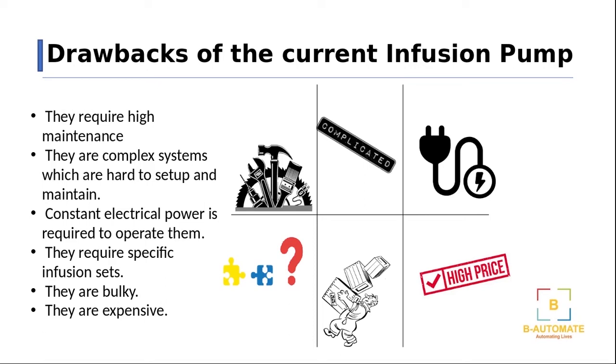Few attempts were made to overcome the drawbacks. The traditional method of infusion was replaced by using embedded system technology, a system for detecting the variations in light transmission between a LED and a photodiode placed around the IV drip chamber to monitor IV drops. This system was designed to run with a battery, but it does not have a battery regulator to save the battery power. Another IV drip monitor based on optical sensor called AccuFlow was commercialized, and the device displays the flow rate and has alarms which operate when the rate deviates from preset value.